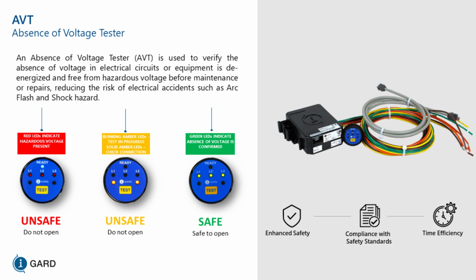And only if you get less than 3 volts phase to phase and phase to ground, and everything is connected properly and working properly, you're going to get 3 green lights indicating that the point at which you have the conductors connected is de-energized.